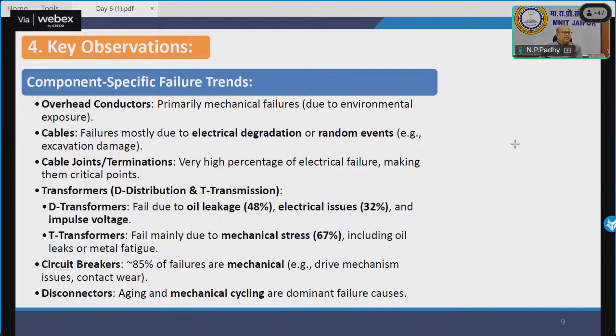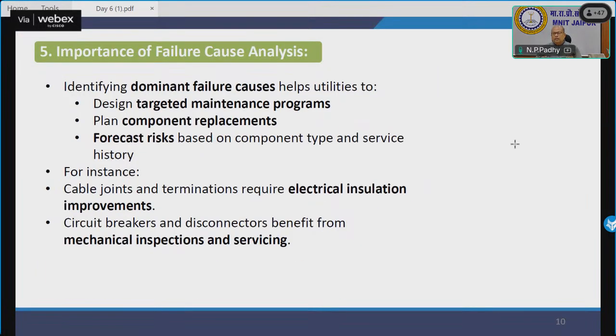So once you know this analysis, especially for any distribution system, these are the factors that need to be calculated, and hence the maintenance approach, reliability study and investment need to be planned. Identifying dominant failure causes helps the utility to design targeted maintenance programs, plan component replacement and forecast risk. For instance, cable joints and terminations require electrical insulation improvement. Means cable joints and terminations, you realize, fail because of electrical insulation. So that means at regular intervals, we need to check the electrical insulation of these conductors from time to time.